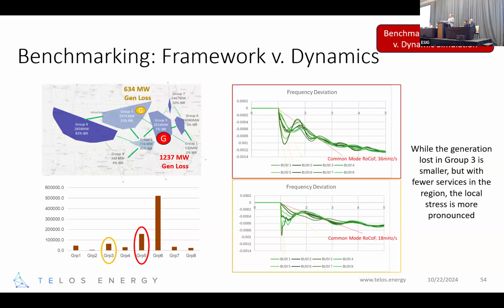But what you can see is the individual groups take a different ride on these. And in fact, you notice on the bottom graph that several of the groups actually have a local frequency excursion and quite high RoCoF that exceeds what you saw from the loss of the larger unit. That's an interesting indicator that even though the need for the service was not as great for this contingency, based on the location at which it happens, it can actually stress that system locally more.